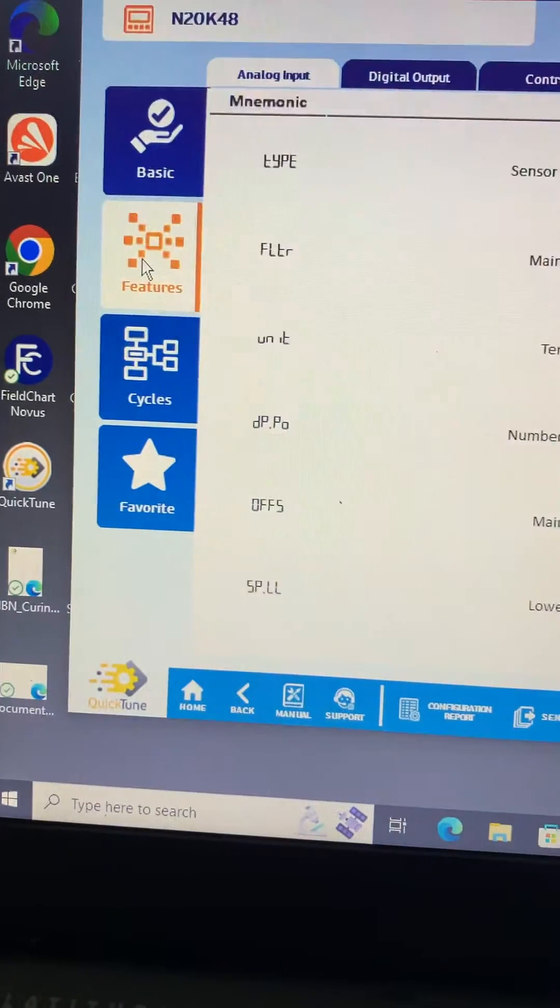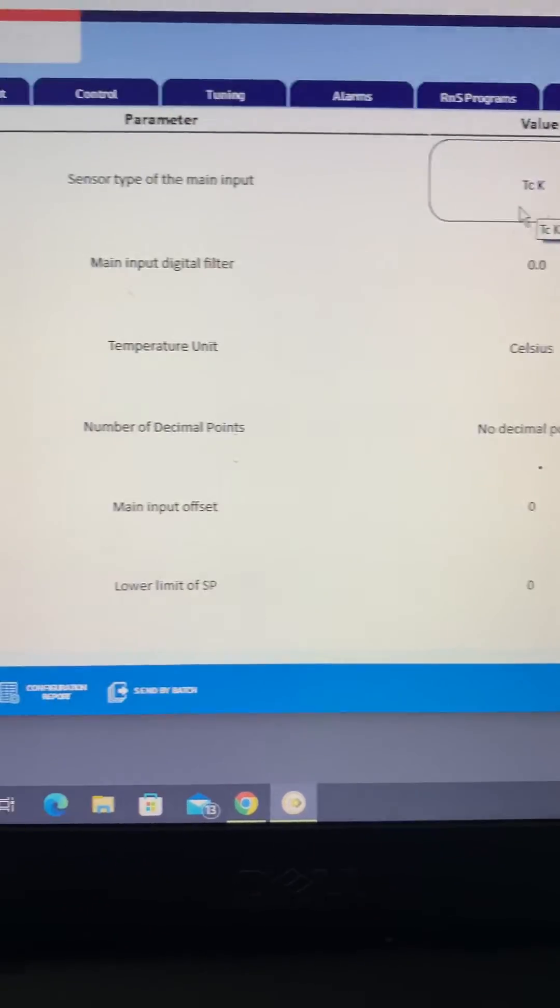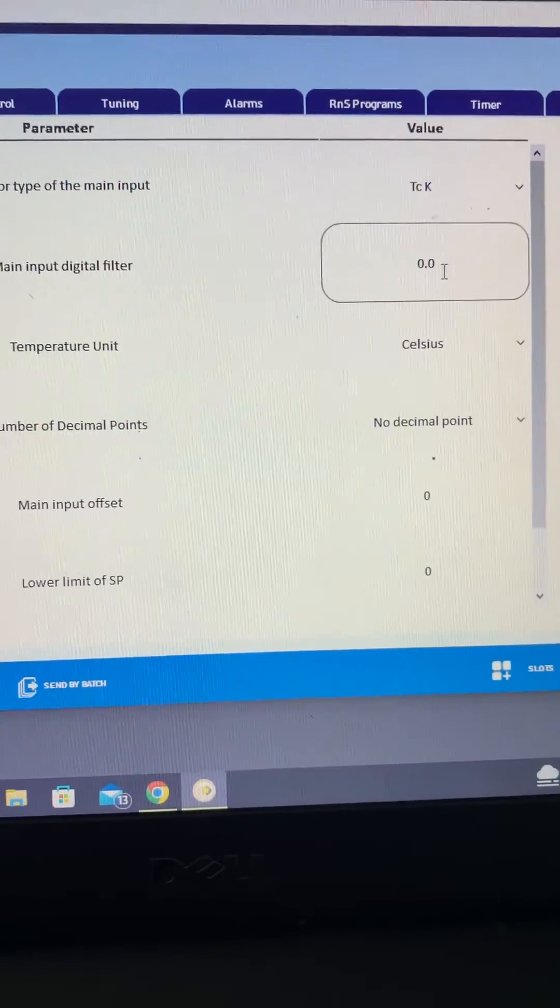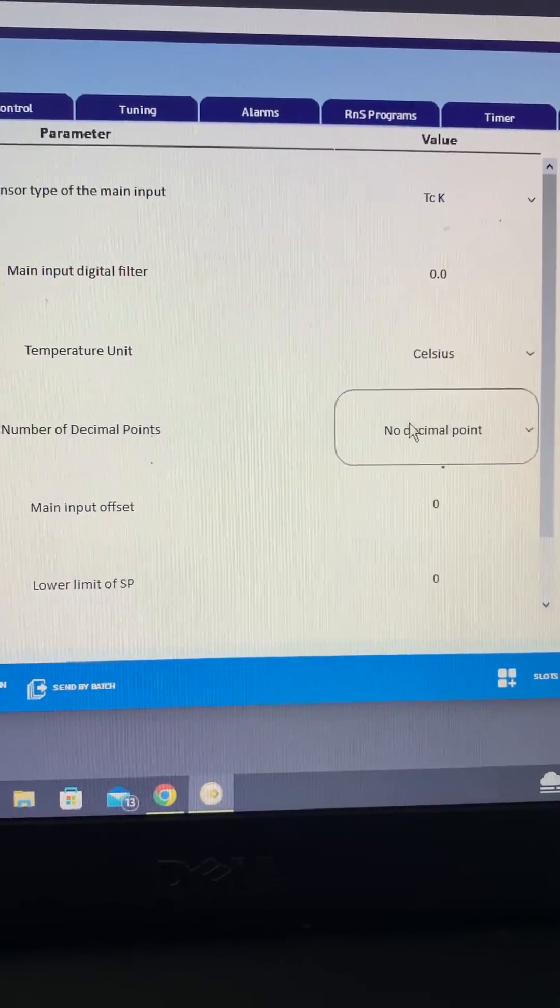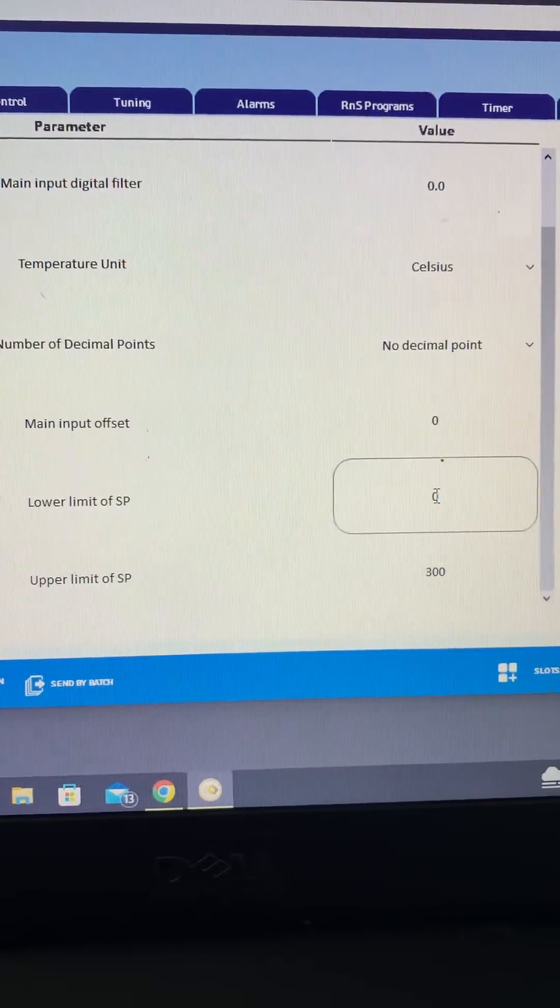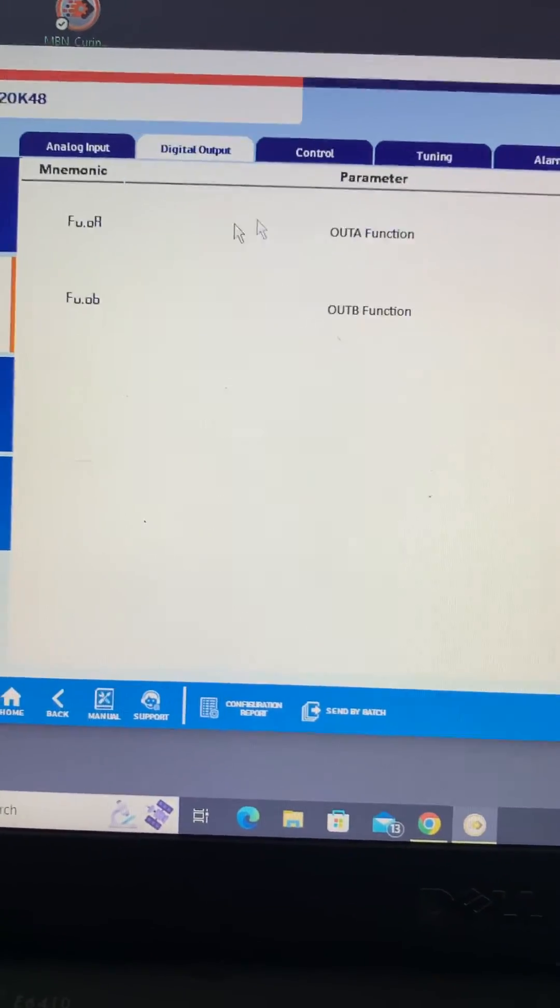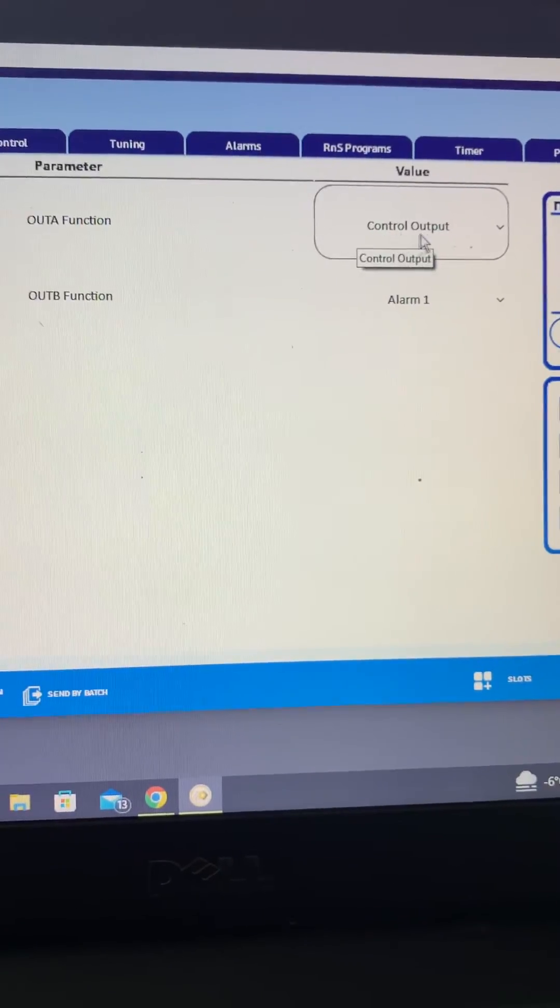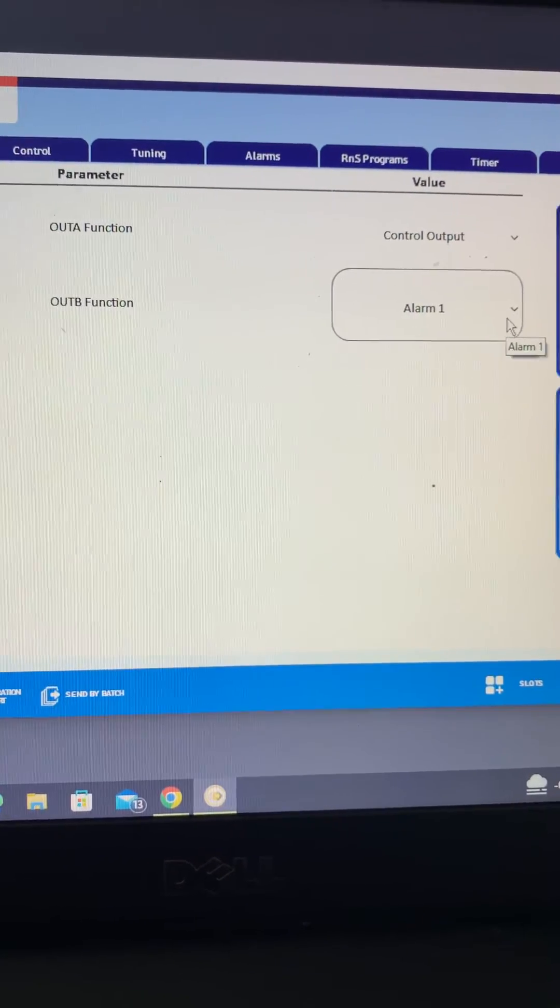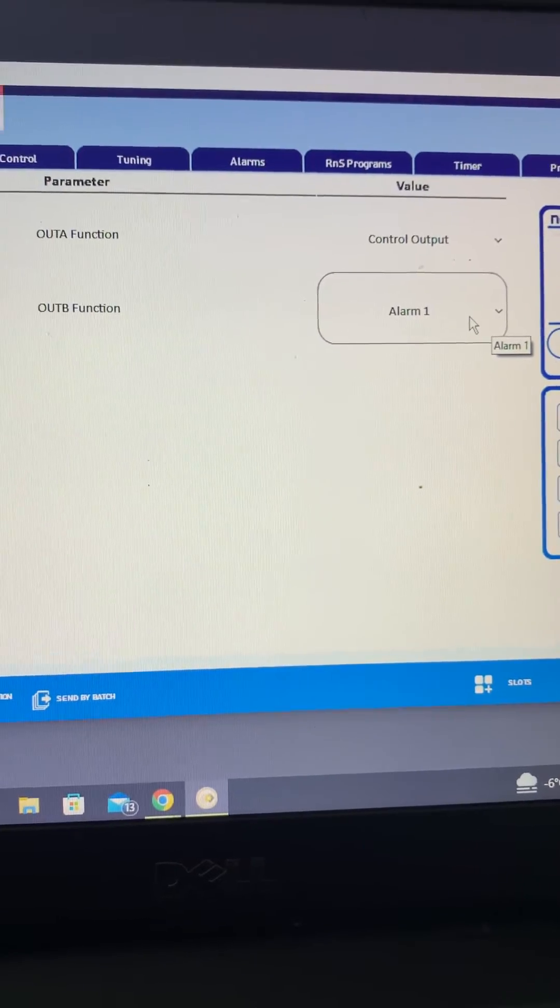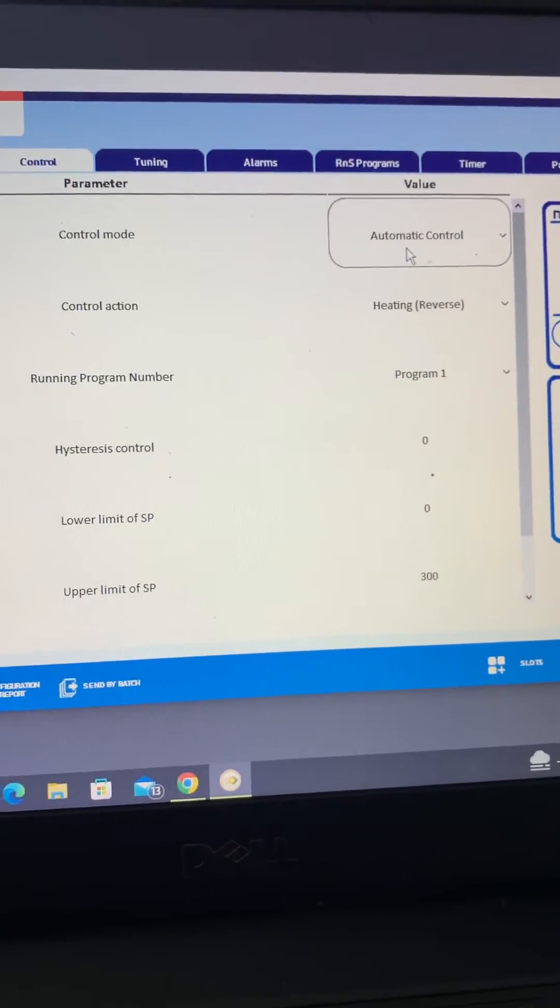We're going to move over now and have a look at the features. A lot of these are duplicated. You can see we've got a type K, we're not filtering the input signal. Celsius, no decimal points, no offsets. Lower limit of zero is fine. And then here is where we've configured our output, so output A as the control output, that's going to be your pulse to the solid state relay. Output B is going to be a relay contact to bring that fan on into control.